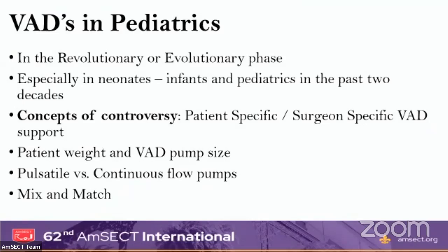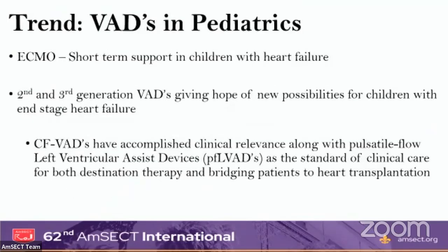So pulsatile versus continuous flow pumps, this is the whole comprehensive idea about all the VADs available in the market now. Mix and match approach is widely extended in the pediatric population. I also mentioned this during my moderating session at the plenary session yesterday, when Dr. Wells mentioned the continuous flow and the pulsatile flow, because we start with pulsatile, switch to continuous, again come back to the pulsatile, then right side is continuous flow, left side is pulsatile flow. These are all the combinations we have been working through in the past almost 10 years.